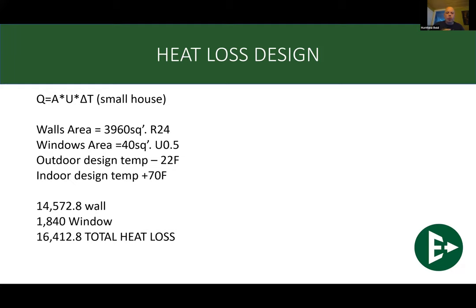So what we do is we do the whole thing all together. So with my 3,960 square feet of wall space, that's 14,572 BTUs required for the walls. For the windows, 40 square feet of windows, we're going to do the formula, Q = A × U × delta T, 1,840 BTUs required for all the windows. So the whole home requirement for the heat loss is 16,412. Now, one thing I didn't add into this equation is ceiling and floors.